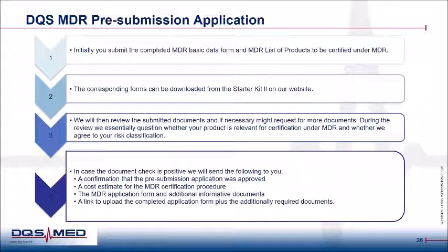So competency is a very intense subject for medical devices, and the grouping of the medical devices is also very intense. During the application, we have to review all this information, and it's very important at that point that the basic data are always filled in completely. The more complete the basic data, the better the chance that we can go through the pre-evaluation on the first run. If we cannot, we would have to do several instances, which means going back and forth. As medical device regulation requirements are intense for us, this will cause permanent delay for all of us. So the more complete the basic data we get, the better we can do the evaluation on the first run.